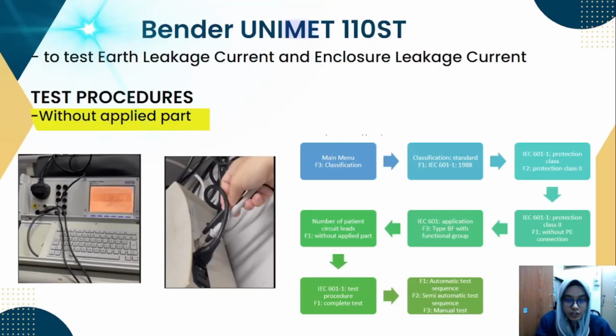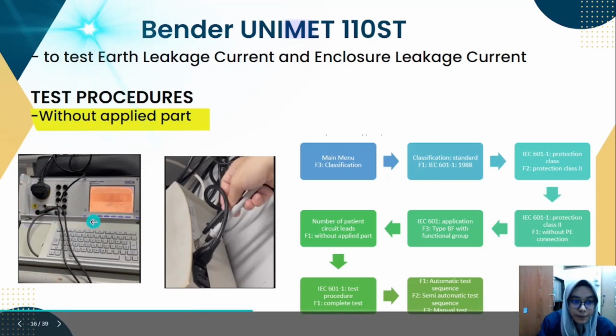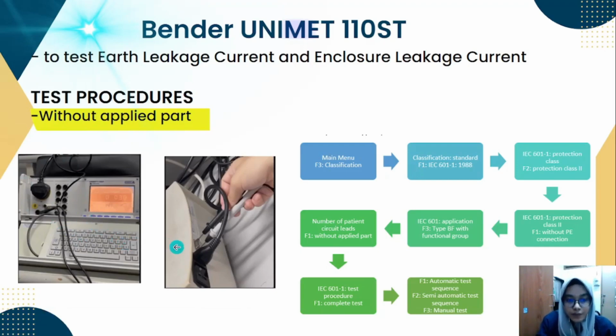First, to test the earth leakage current and enclosure leakage current, we will use Bender without applied part. So first, the Bender safety analyzer is turned on, and the 3-pin power plug of the tonometer is connected to the Bender, and we have 2 probes connected to the conductive part and the earth of the tonometer. Then, the following option can be chosen on the Bender monitor to start the test.